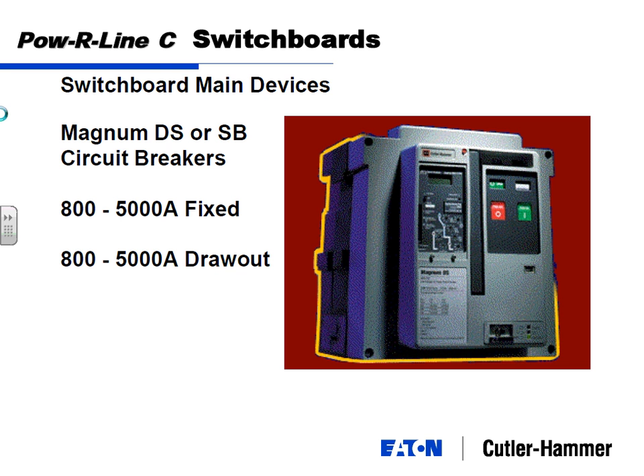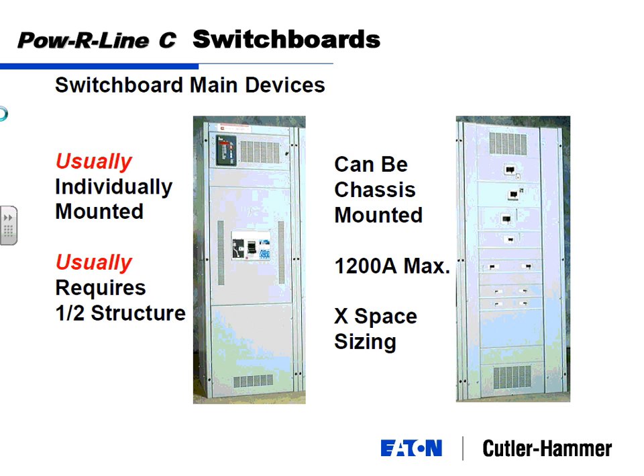They also have the ability to do draw-out or fixed on those breakers, on the Magnums. So while you can chassis mount a main device, just like on a power distribution panel, most switchboards are going to be individually mounted. So they'll mount the main breaker somewhere in the structure and take up a third to a half of the structure.